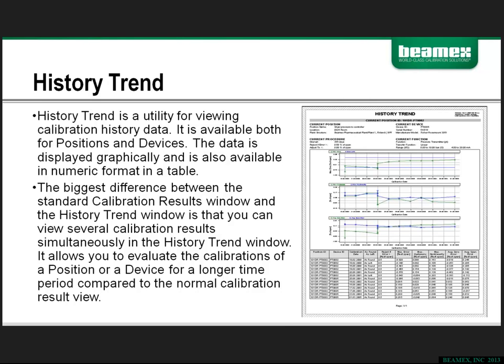So the biggest difference between just looking at a calibration certificate, which just gives you the standard results, and the history trend is that you can view multiple calibration results at the same time. So by looking at the graphical overlay of all of the history of that particular device, it really gives you a much broader picture in terms of how it performed.